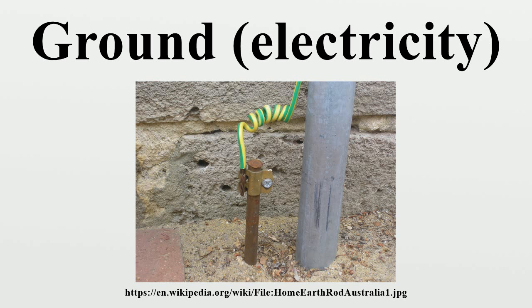High-resistance grounding systems use an NGR to limit the fault current to 25A or less. They have a continuous rating, and are designed to operate with a single ground fault. This means that the system will not immediately trip on the first ground fault. If a second ground fault occurs, a ground fault protection relay must trip the breaker to protect the circuit.